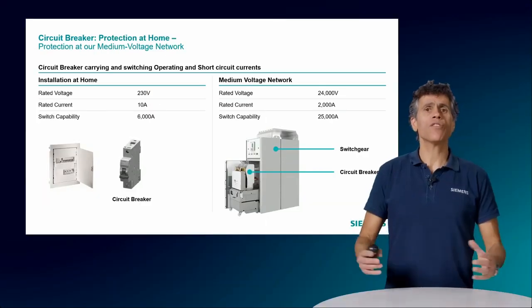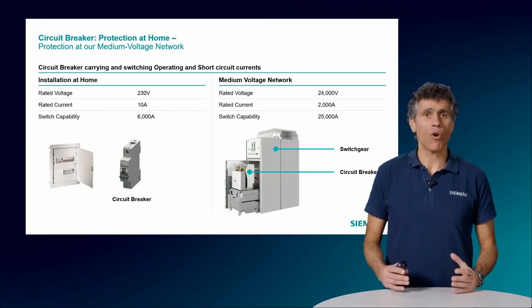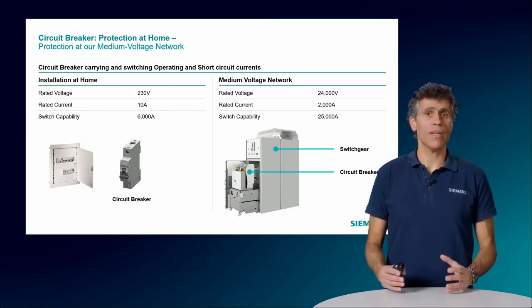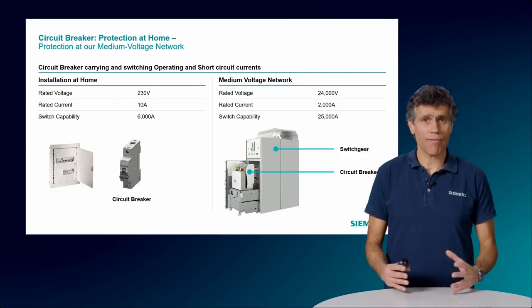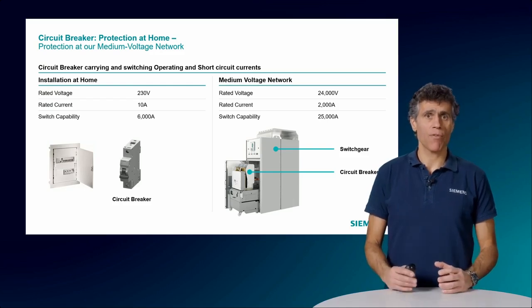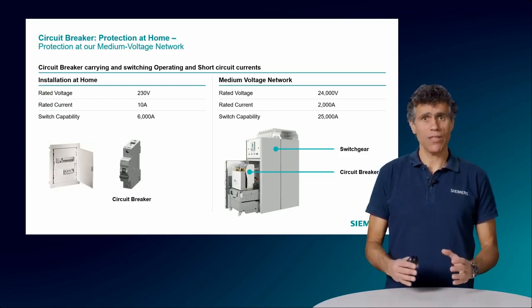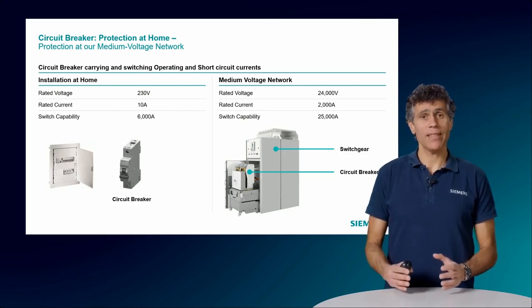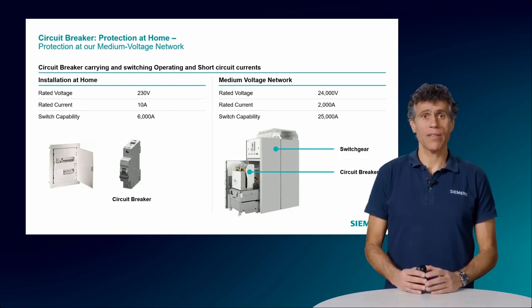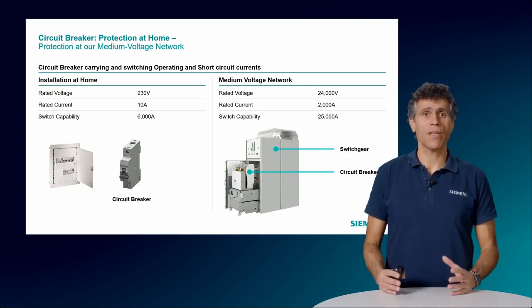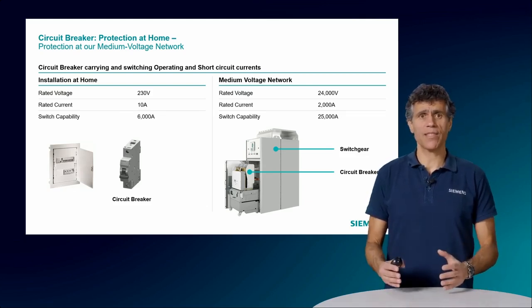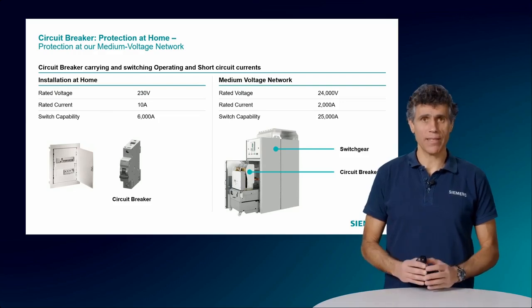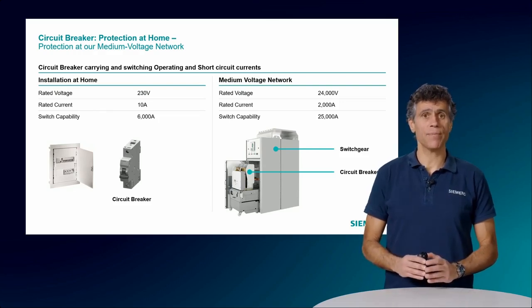So why are circuit breakers that crucial? In order to assure that current flows, they must handle everything in every possible condition, from normal duty to inductive or capacitive currents and full short circuit currents when faulty conditions occur. Their ability to make or break connections under every possible fault condition, be it an earth fault, phase opposition, etc., is crucial for maintaining system integrity and safety.